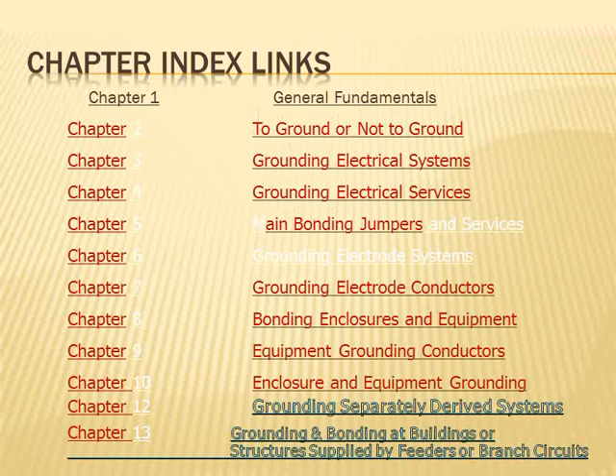And the third one is the in-between, a hybrid between grounded and ungrounded. The smarter folks years ago said, well, the grounded system has these advantages and disadvantages, and the ungrounded system has these advantages and disadvantages. So what if we come up with a system that is a cross-reference, or a hybrid, between the two? That hybrid is called the impedance grounded system, which is the best that you can have in terms of survivability of your power system, on high voltage as well as in manufacturing and assembly lines and so forth.